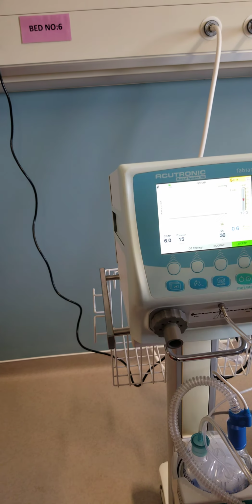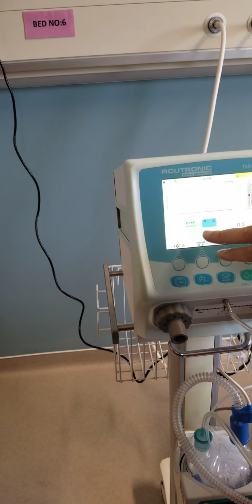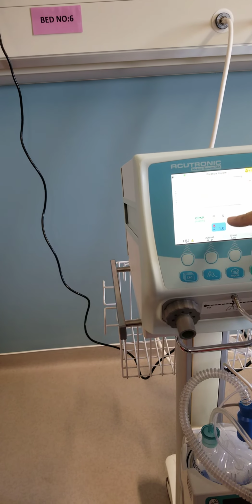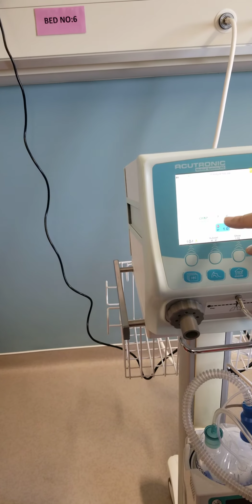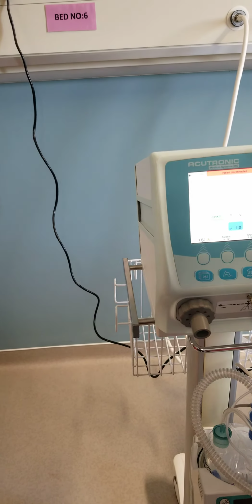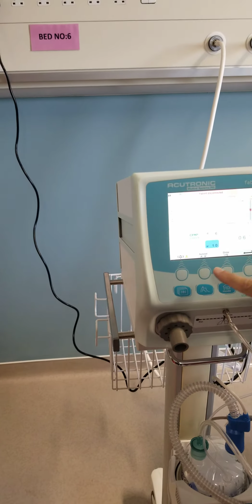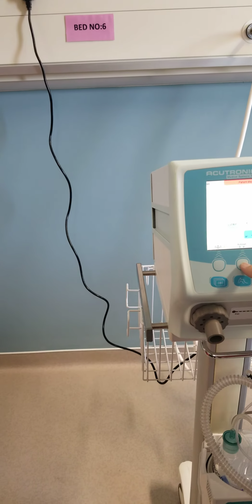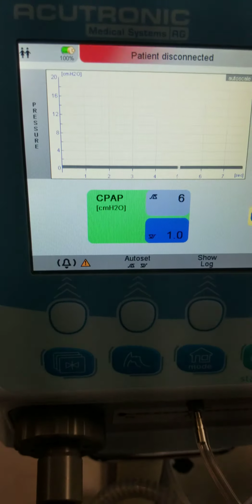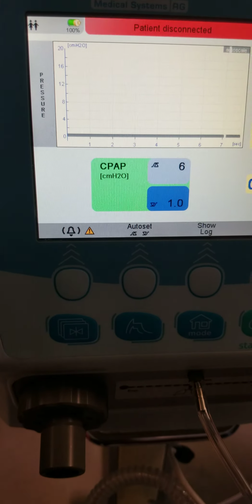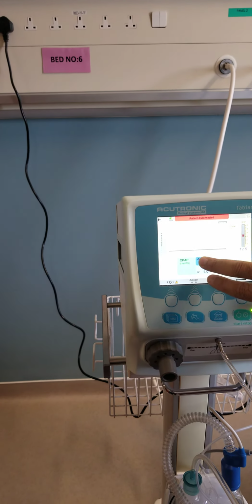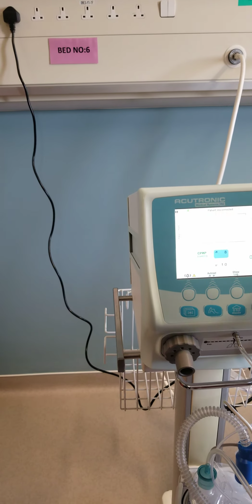Well, you need to alarm. Okay, now I'm on oxygen, right? CPAP. Yes. So now I'm in CPAP mode, and for CPAP, you have your lower alarm limit, high alarm limit. So this is where you set. Now either based on the baby's condition, you can directly go for an auto set. So if I press auto set, automatically it will select. If the baby is already giving, it will keep 2 below or something. Or I can go for a manual.